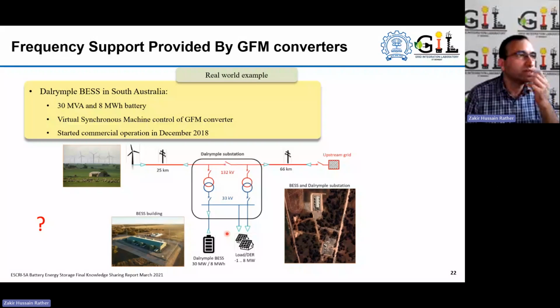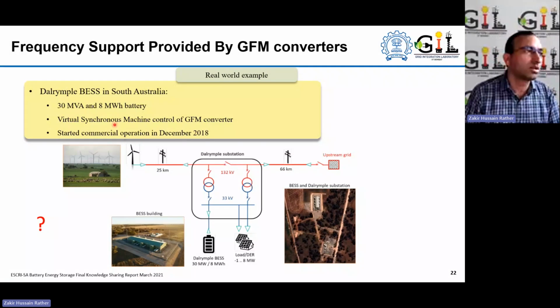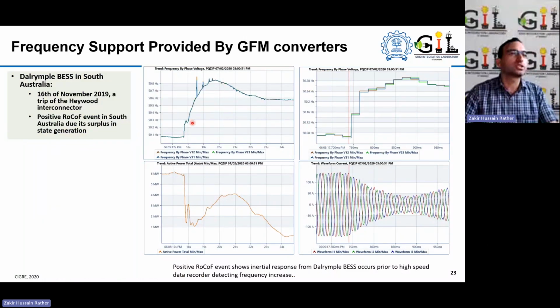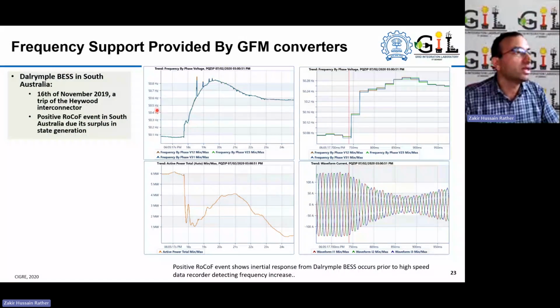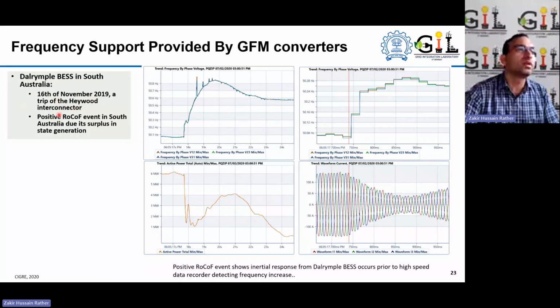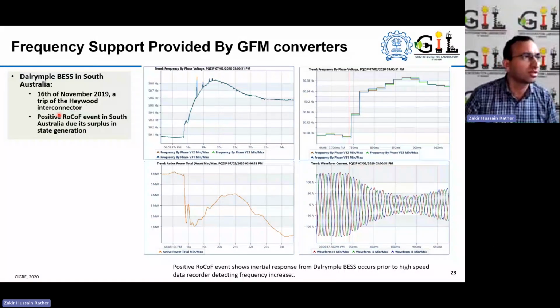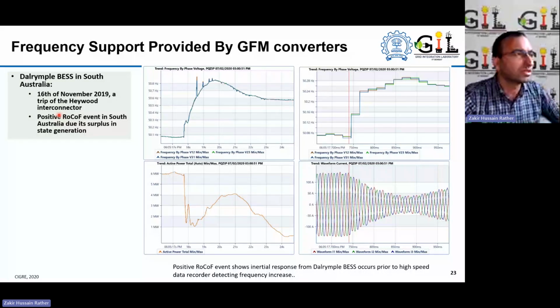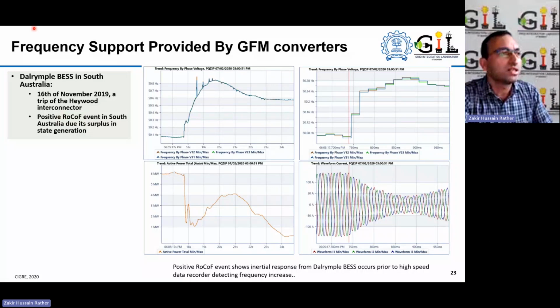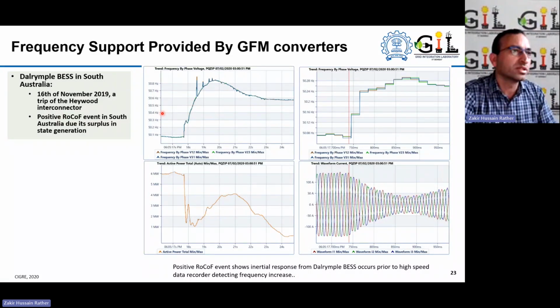Similarly, there is one more field example of a battery energy storage system with grid forming technology interfacing, which is again VSM mode of the control, a 30 MVA, 8 megawatt hour battery. This is the response of this battery storage plant in the South Australian grid on 16th November, where there was a trip of the Heywood interconnector. Those who are following these kinds of events, in 2016 this Heywood interconnector was also partially involved in that grid outage.